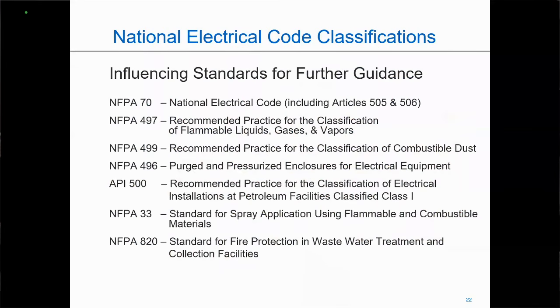And so there are some areas that you can go to for further information. When you're looking at NFPA 70, some of the specific applications, which are Articles 510 through 516 that cover gas stations, aircraft hangars, and spray booths, will give exact information as far as classifying. But unfortunately, the lion's share, the majority of our applications, don't fall within those articles. So a place that you might want to go is NFPA 497, the recommendation for classification of areas containing flammable gases, liquids, and vapors. API 500 also falls within gases, liquids, and vapors. For combustible dust, NFPA 499. So there are various places you can go for further information as far as classifying areas.